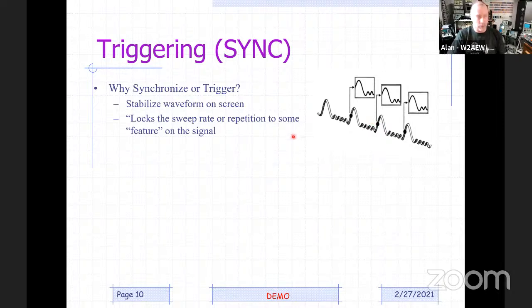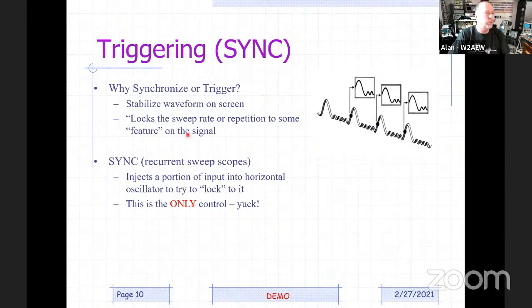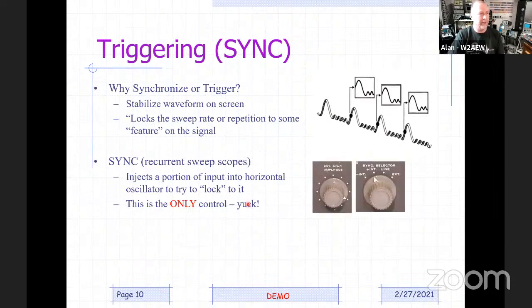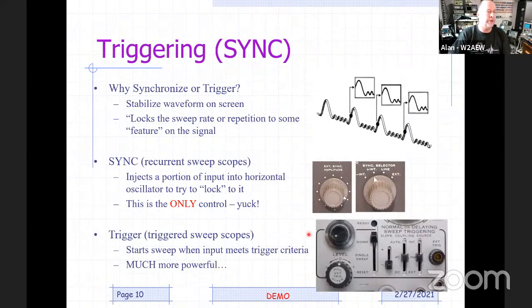Okay, so with the old recurrent sweep scopes, there was a sync control, and what that would do is take a portion of the input signal and inject it into that horizontal oscillator to try to injection lock it, and that's the only control you had. It's just horrible. This is kind of what it looked like. You select an internal sync source, and the sync amplitude controlled how much of the input signal you'd inject into that oscillator. And you'd have to mess around with the horizontal oscillator vernier and this control to get a stable waveform. It's just horrible. Don't bother. Don't use those. Use a triggered sweep scope.